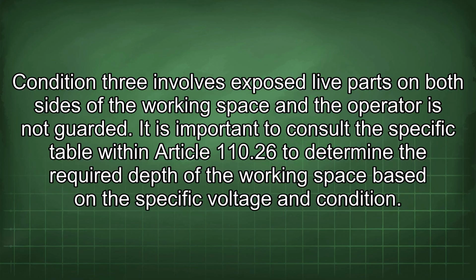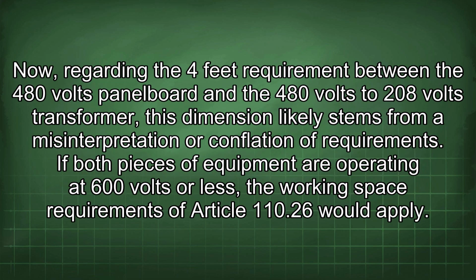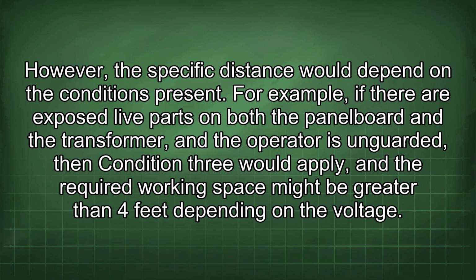It is important to consult the specific table within Article 110.26 to determine the required depth of the working space based on the specific voltage and condition. Now, regarding the 4 feet requirement between the 480 volts panel board and the 480 volts to 208 volts transformer, this dimension likely stems from a misinterpretation or a conflation of requirements. If both pieces of equipment are operating at 600 volts or less, the working space requirements of Article 110.26 would apply. However, the specific distance would depend on the conditions present.